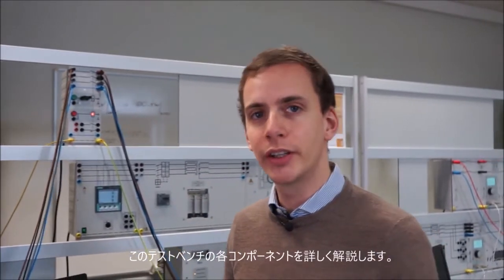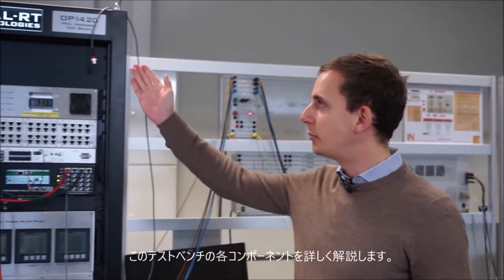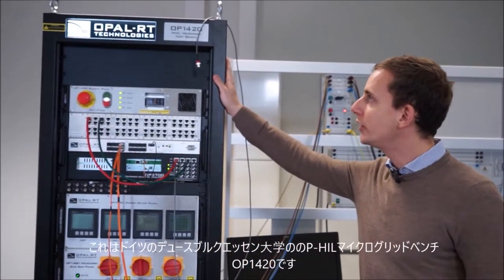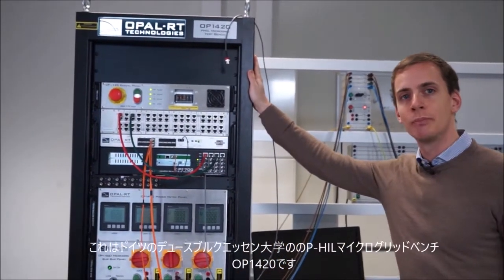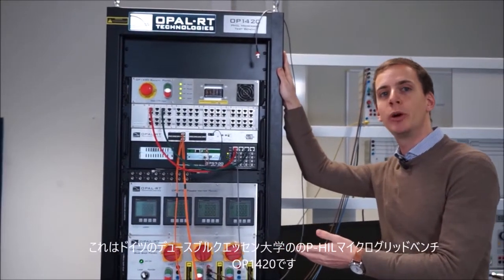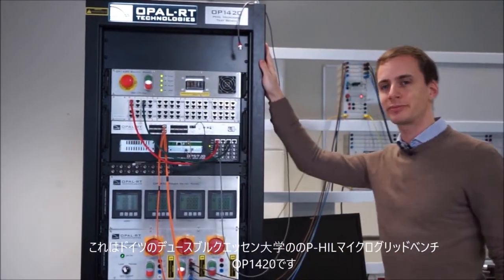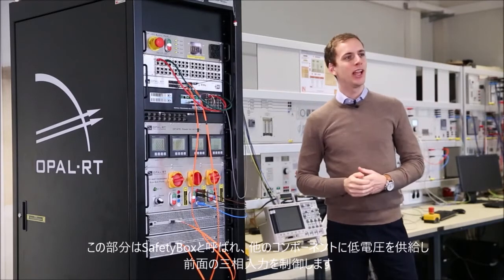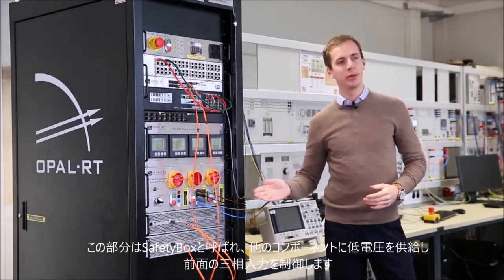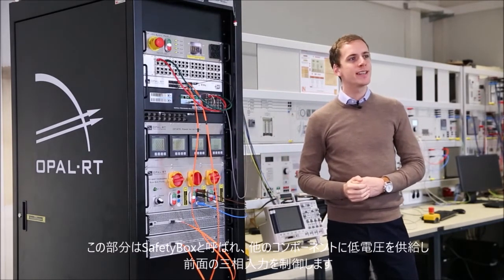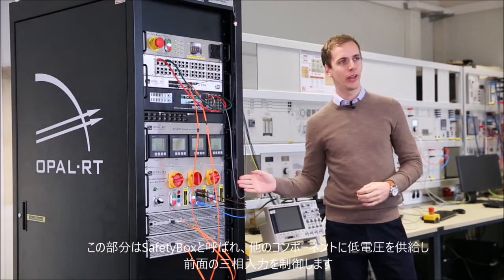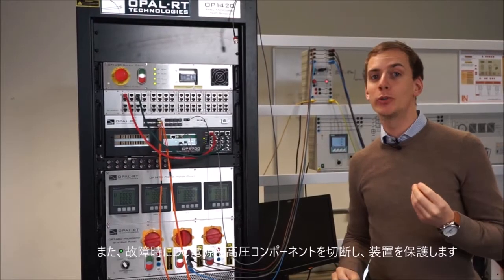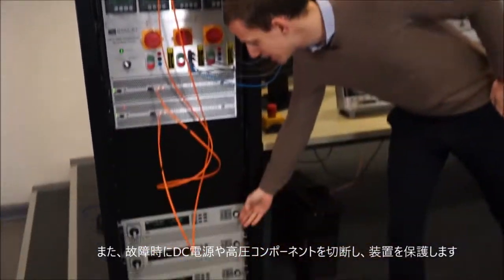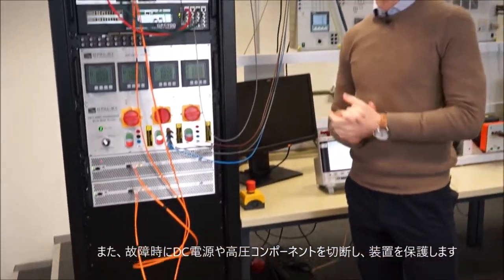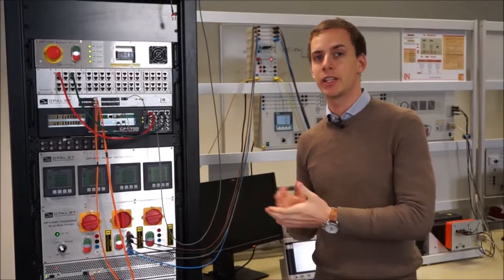I think now it's time to have a deeper look at each component of this test bench by looking at the OP1420 PHIL microgrid test bench in University Duisburg-Essen laboratory. This safety box provides low voltage supply to other components and controls the three-phase input power on the front side. It also allows to disconnect DC sources and high power components of the test bench in case of fault.